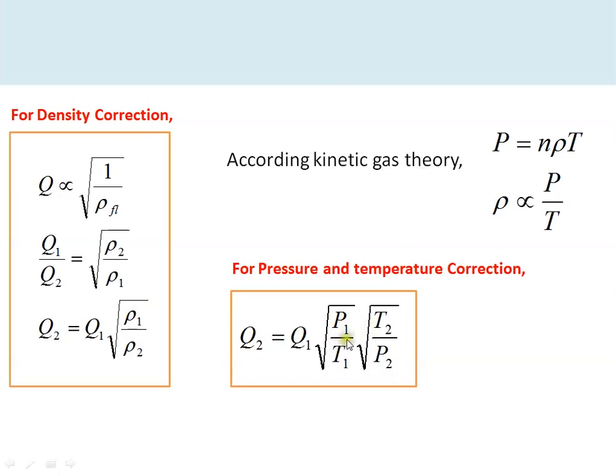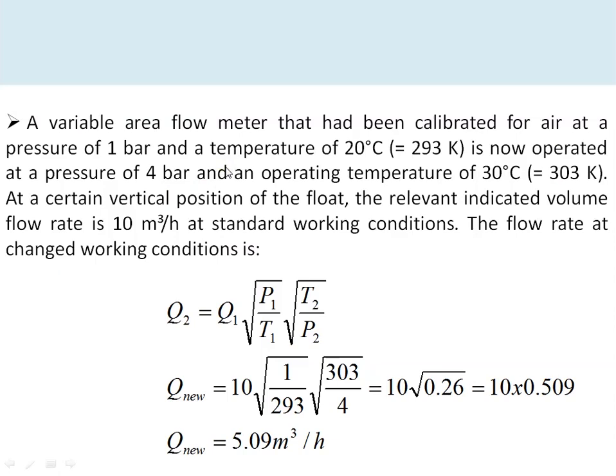To correct for both pressure and temperature variations, we use the kinetic gas theory, which states that pressure P is proportional to the number of molecules times density times temperature, giving density ∝ P/T. Substituting into the flow equation gives a corrected flow rate that accounts for variable pressure and temperature. As an example: a variable area flow meter calibrated at 1 bar and 20°C (293 K) is now used at 4 bar and 30°C (303 K).